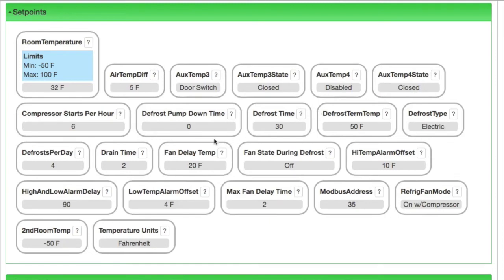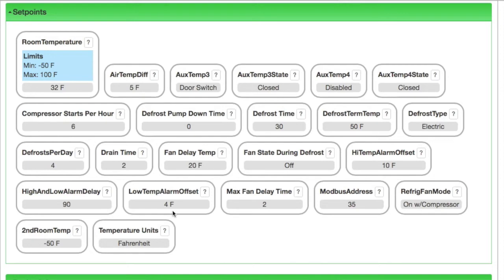Auxiliary temp 4, compressor starts per hour. Then we see our defrost set points: defrost pump down time, defrost time, defrost term temp, defrost type, defrost per day, drain time, fan delay temp, and fan state during defrost. Then high temp alarm offset, high and low alarm delay, low temp alarm offset, max fan delay time, and Modbus address. Refrigeration fan mode, and second room temp set point.